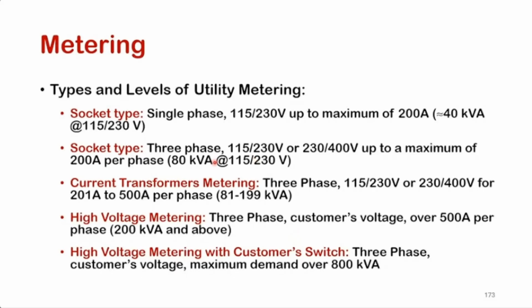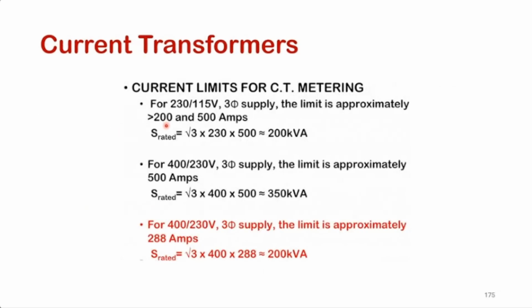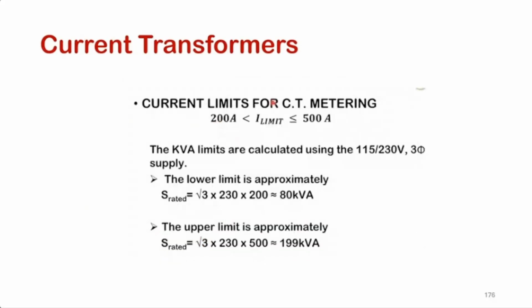So most likely in the exam, you're going to be interchanging between socket type and CTs, right? And the two things will be interfacing with it. Socket type, as I said before, is limited to 200 amps. When you calculate the limits for a CT, the CT could go up to greater than 200 amps, but less than or equal to 500 amps. Yeah, there is a limit for your CT. So your lower limit will be 80 kVA and your upper limit will be 199 kVA. That's how much the CT could measure for this instance.